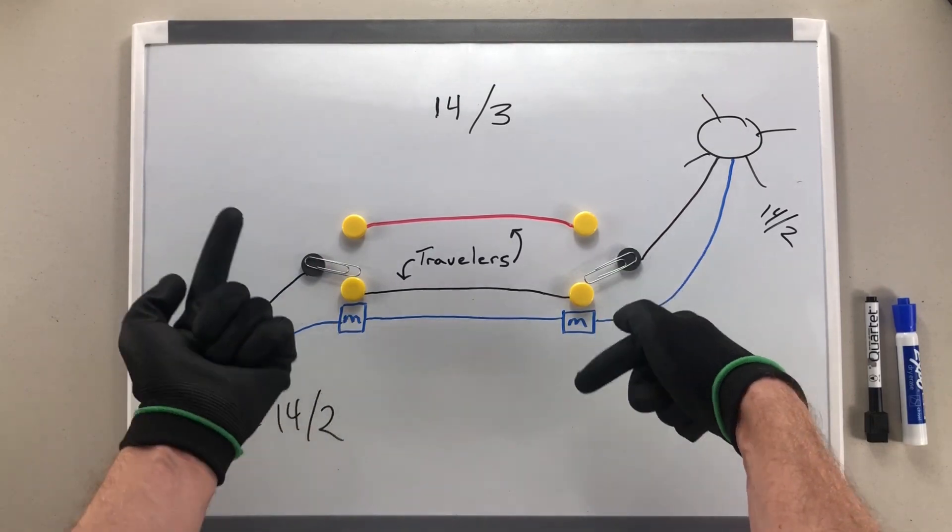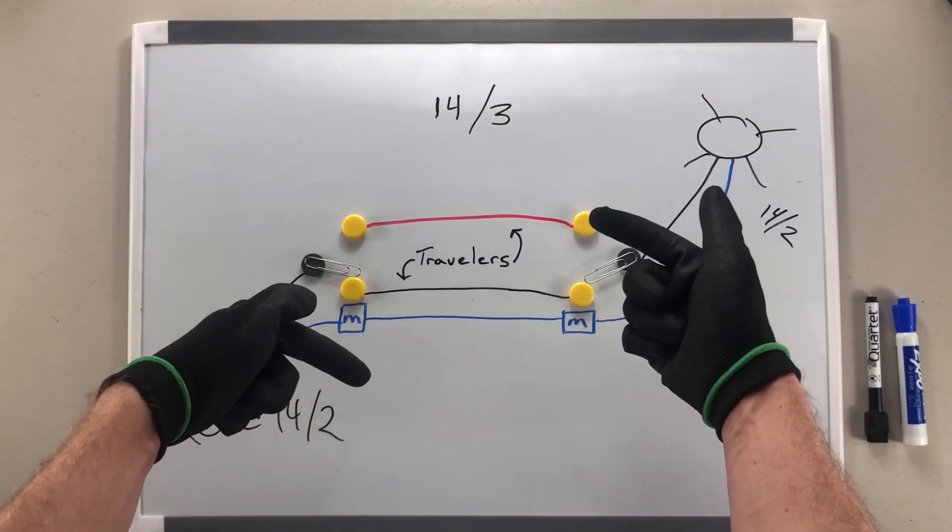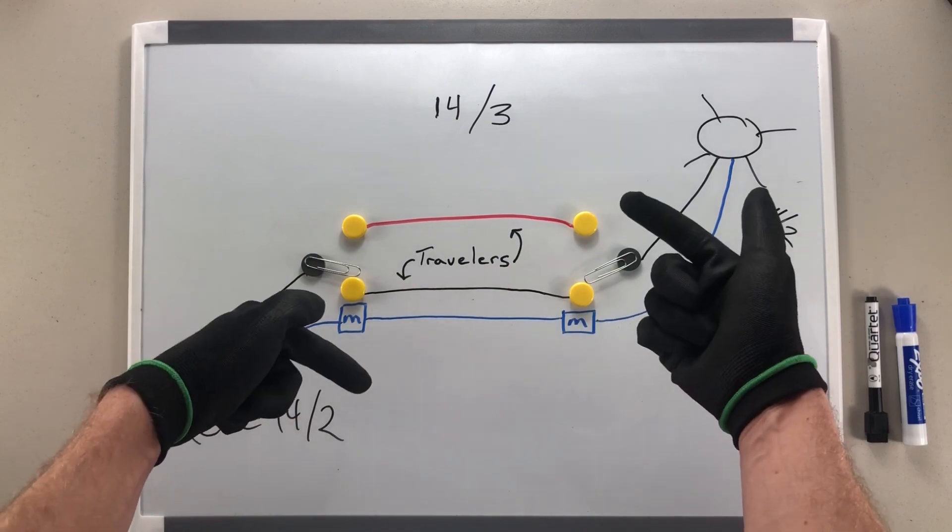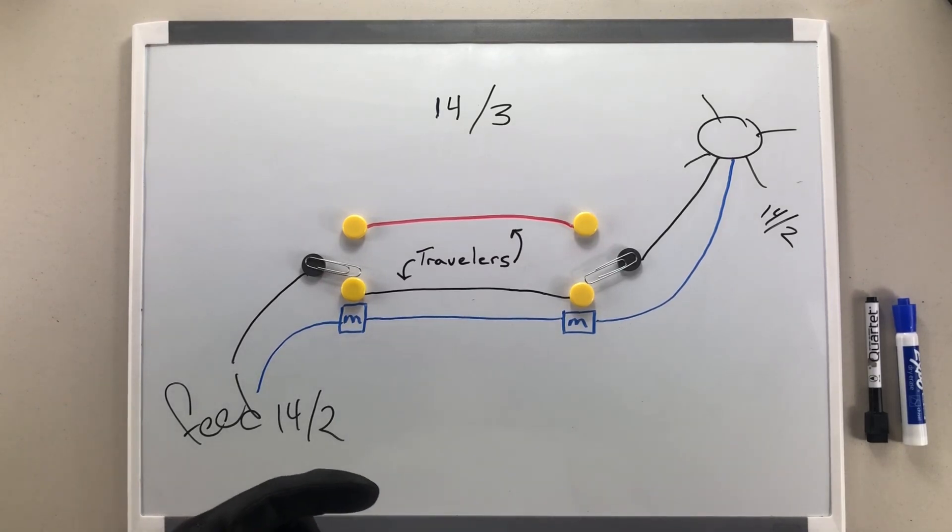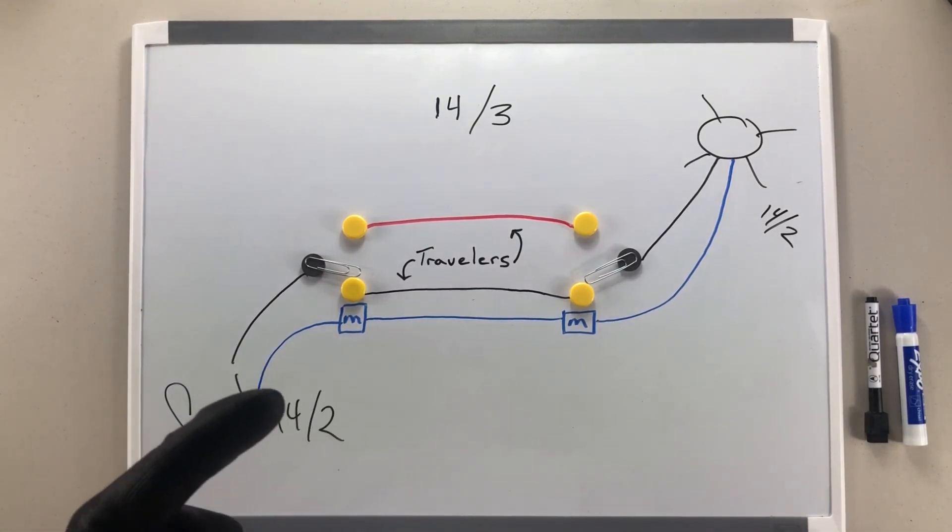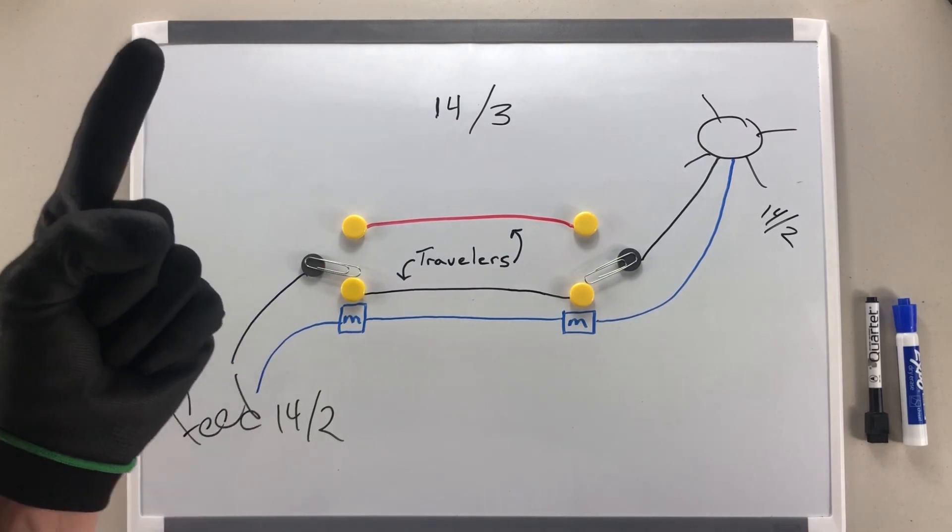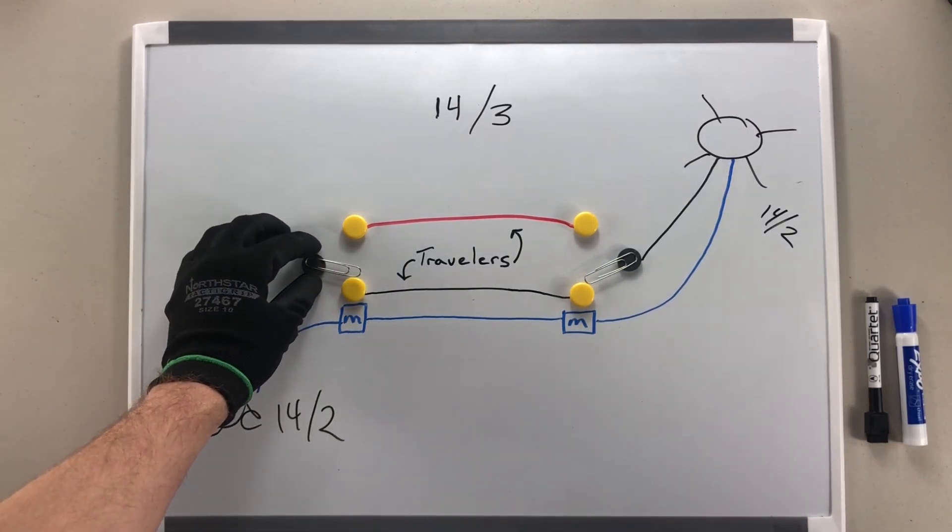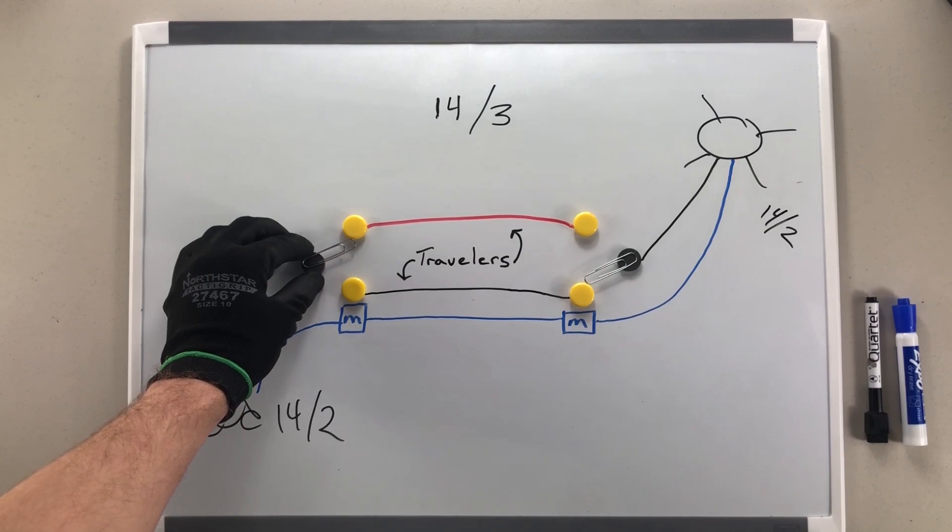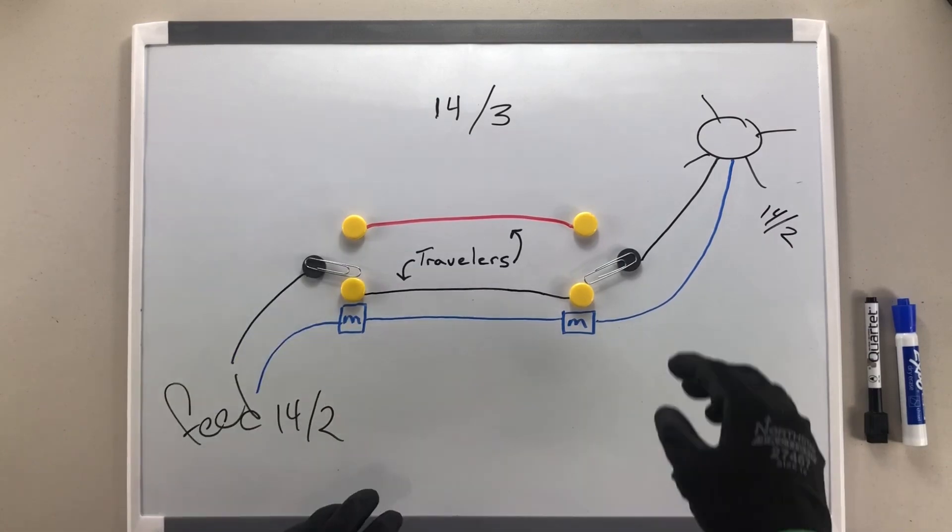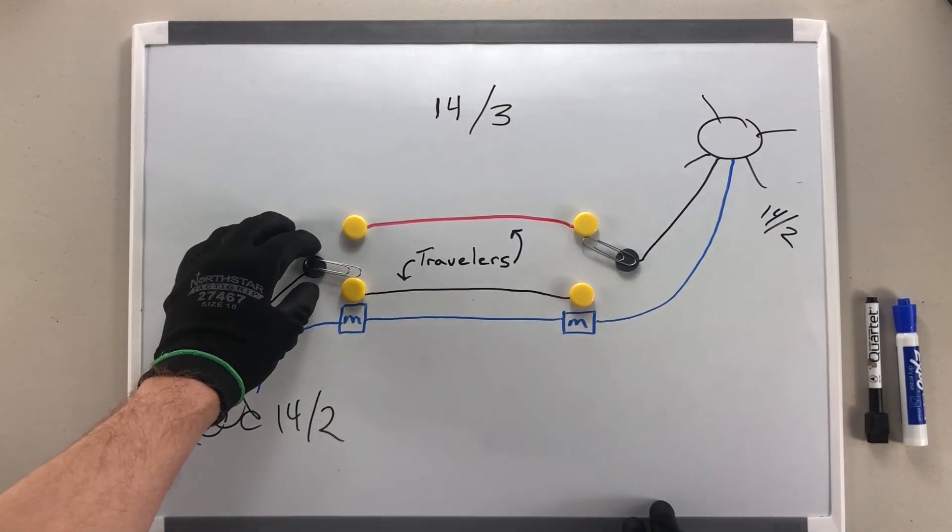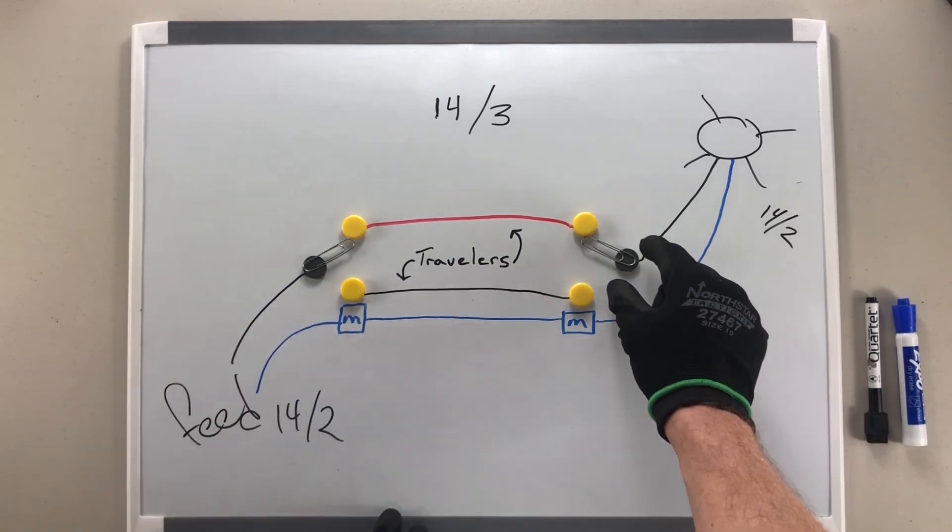Anytime we hit one of these, it will change the condition, being able to turn it on and off from either location. This would be very common, maybe in a stairwell, or in a large dining room where you have two entrances. Unlike simple single-pole switches that have an on or an off, this only has this traveler connection or that traveler connection. There's no such thing as floating in the middle here. You're either here or here, which is why no matter which one of these switches you turn, you'll always have an on or an off condition.